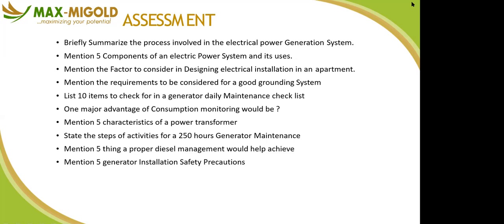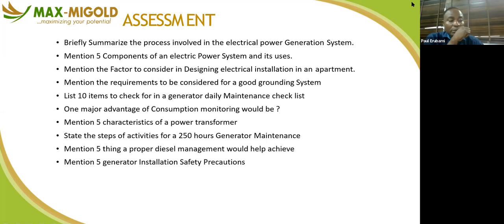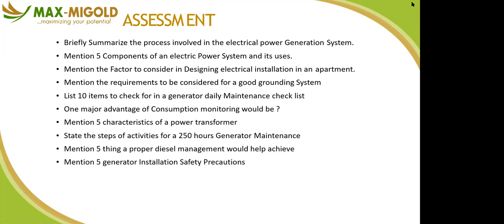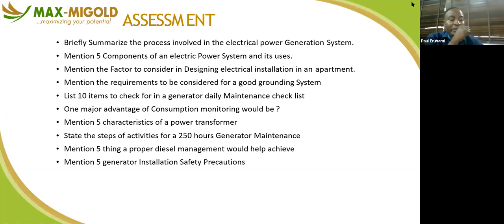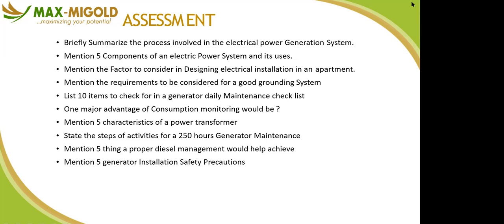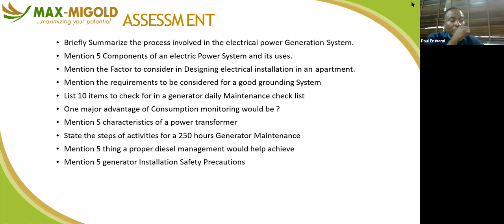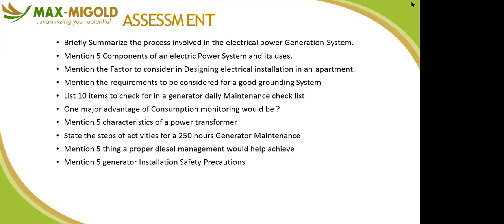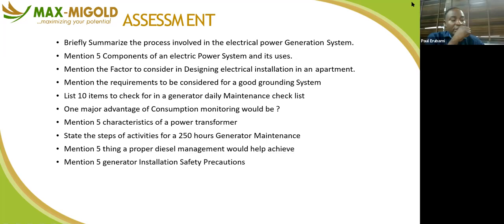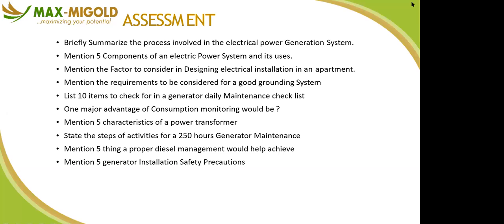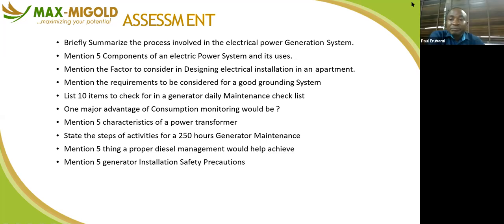No, what I'm saying is, I said a 100 kVA generator produces 80 kilowatts. So for someone producing a peak period of 200 kilowatts, should use a minimum of 300 kVA generator. Yeah, minimum of 300. That 500 kVA she says she has. No, 500 kVA is like 400 kilowatts. Yes. So it's half of that. That's true. So a 250 kilowatt generator will be okay for her. Yeah, let's say 300 to 350 because of future expansion. Yes, yes. So that's just what I wanted to ask. All right, you are right.